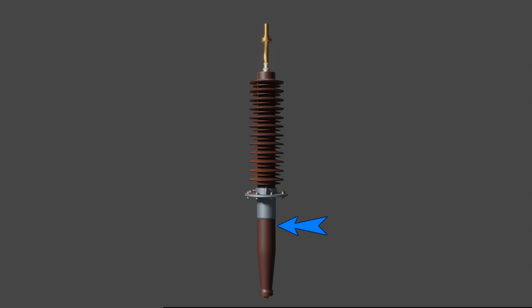The length of this lower portion depends upon the minimum required clearance in the oil from the live bus to the earthed metallic structure or metallic tank. Here, since it will be inside the transformer and immersed in oil, creepage distance need not be maintained. So there will be no atmospheric shed or rain shed. It is plain, you see.